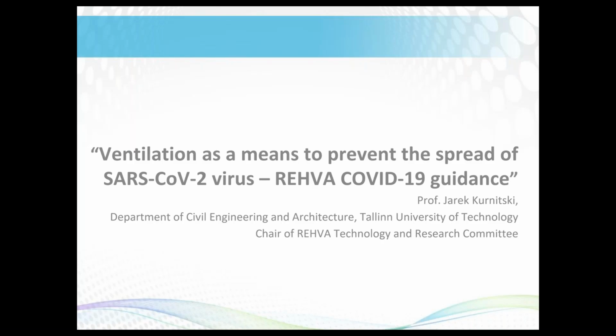Yes, isolation rooms operate with 12 air changes per hour. And indeed, there is, but when we speak about the aerosols, these aerosols basically do not have any settling velocity. So what you can expect is a mixing ventilation, and actually the location of air diffusers is not so important. There is indeed some evidence if we go to larger droplets, so these will settle down, and underfloor air distribution is typically not recommended or seen as not a good air distribution solution when you have particulate matter in the air which will have a settling velocity.